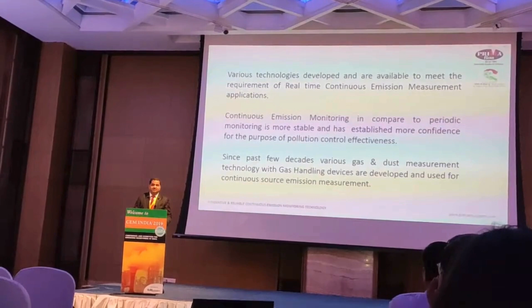Most important, compared to periodic monitoring, I always believe that the purpose of the CEMS should not be related only to pollution emission measurement. It has to be related to your process and your controlling device efficiency measurement. That will give you a good payback. As a businessman, when the industry installs the system, the purpose has to be defined as process efficiency also for the pollution control device that you have installed.